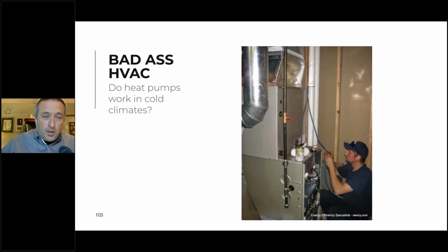They put it in, and Ted got a phone call from his mom: 'Hey Teddy, everything's okay, the house is heating, but the air coming out of the vents is really cold.' It was about 5 degrees outside, which is design temperature for Rochester, New York, also actually Cleveland.